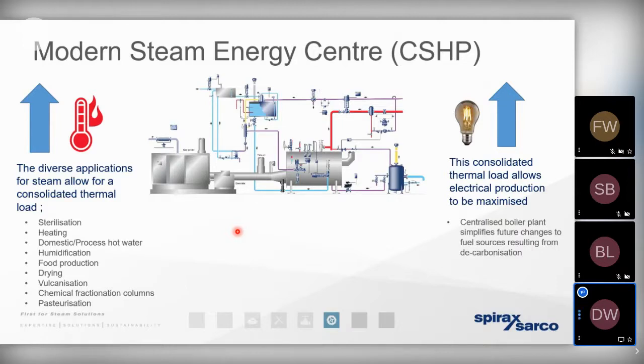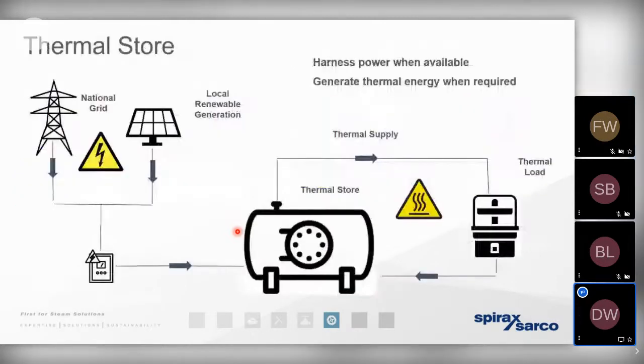And I just want to leave you on one last thought. Traditionally, we've always considered that steam is to be generated utilizing fossil fuels. And we also know that the flash steam principle that we spoke about is where steam can be generated simply by reducing the pressure of a high temperature liquid such as condensate. It means that we can now generate steam by using renewables. It could be heat pumps, it could be aerothermal, it could be solar panels, or it could come from the grid.